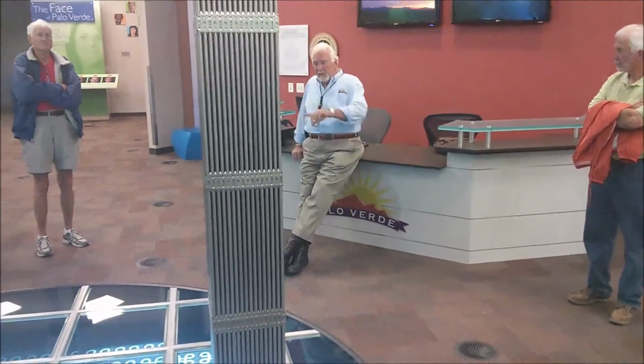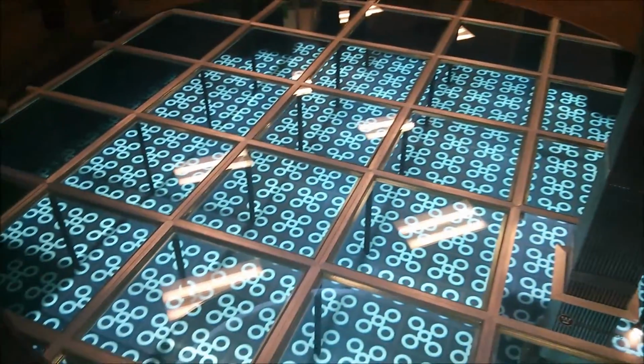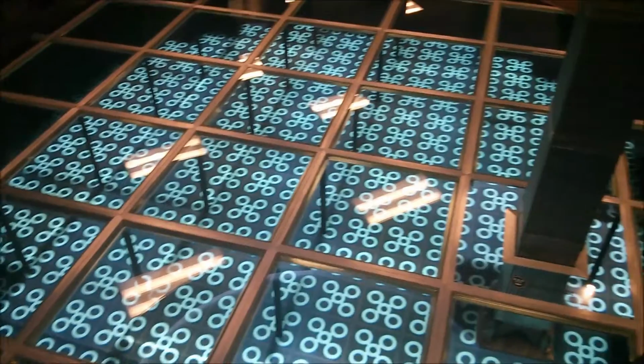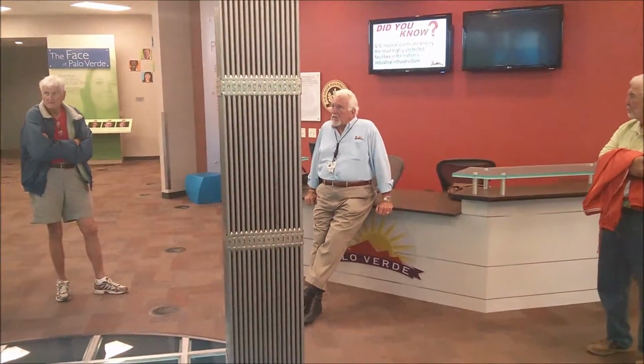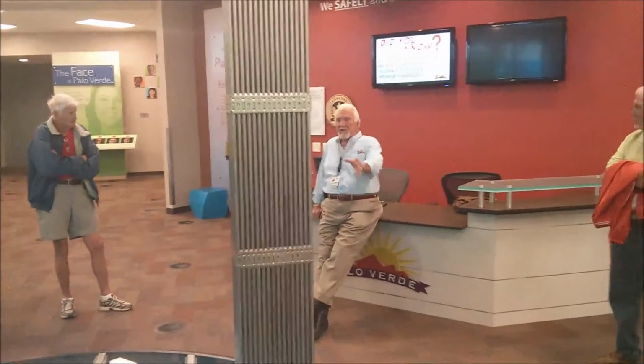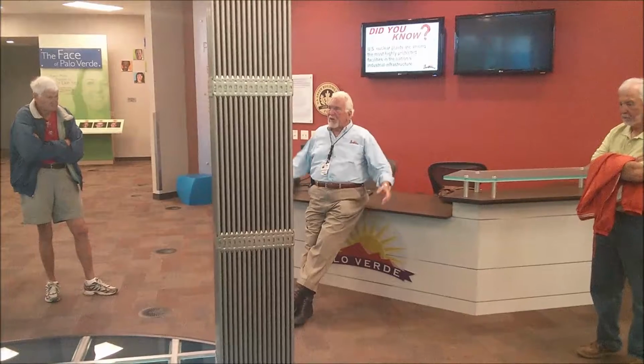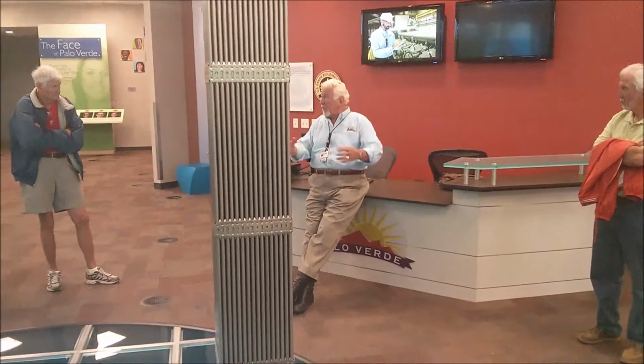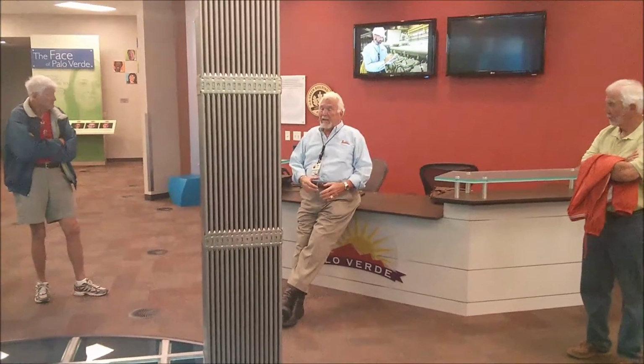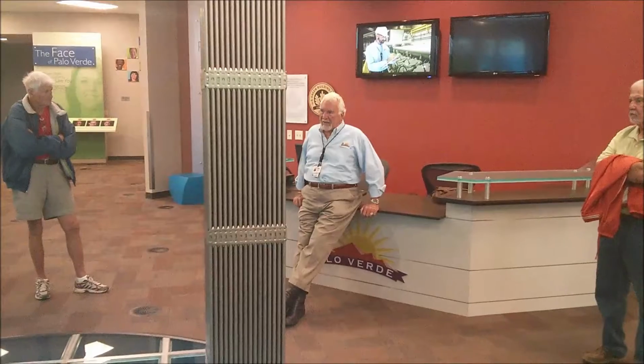So, 241 fuel assemblies in each reactor. We're designed to run the reactor for a year and a half, 18 months, each of our 3 units. At the end of 18 months, we do shut down and we replace roughly 1/3 of the fuel assemblies that are in there. We reshuffle the rest, basically take the outside ones, bring them to the middle. It's like a big charcoal barbecue fire, okay? And then we'll take roughly 80 fresh new fuel assemblies and put those on the outside.